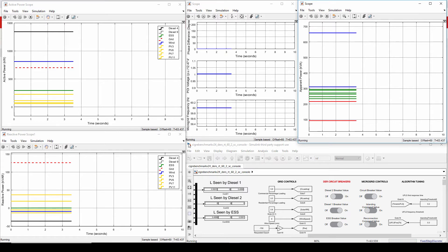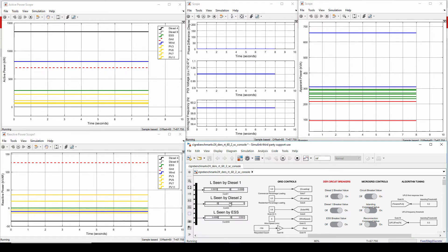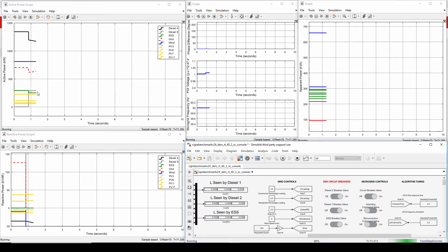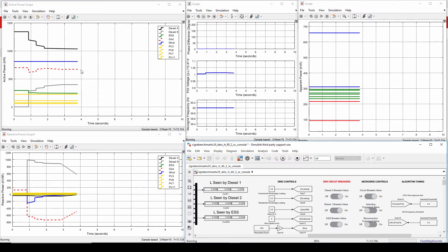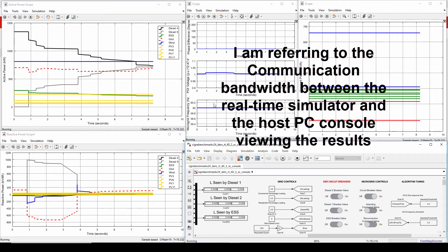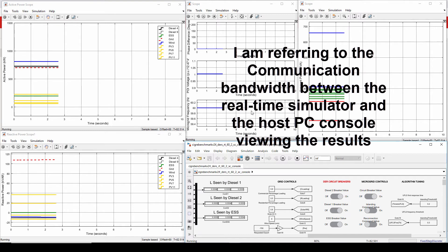And I'm going to start by plug-and-playing diesel 2. So what you will observe now is that the diesel 2 is going to synchronize. The L matrix of diesel 2 is going to update as well as the L matrix of diesel 1 and the ESS. Once it's connected, there will be a little bit of a fallback, but then here, see, it got connected, but then the power from the grid, which is the one in red, is going to be re-regulated back at 700 kilowatts. Now, you see these interruptions. These are just due to communication bandwidth requirements. For me to be able to show the real-time simulation as it's going, so that, for example, when I simulate later on planned islanding, I want to show you exactly how the frequency is varying, with the trade-off of having a little bit of a disconnection.